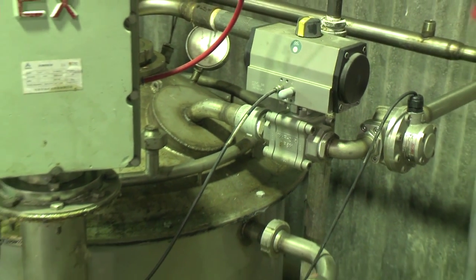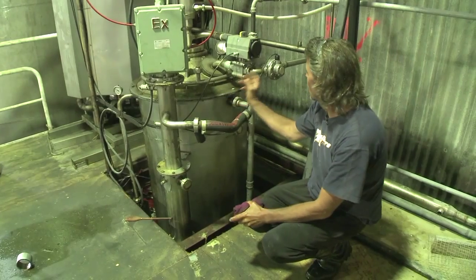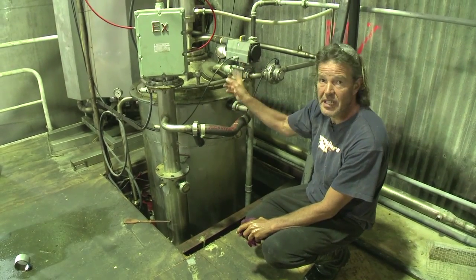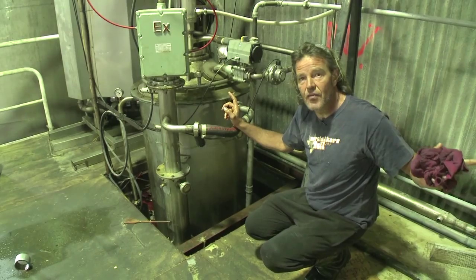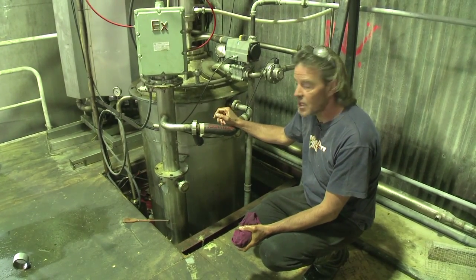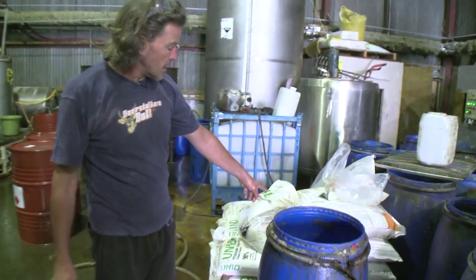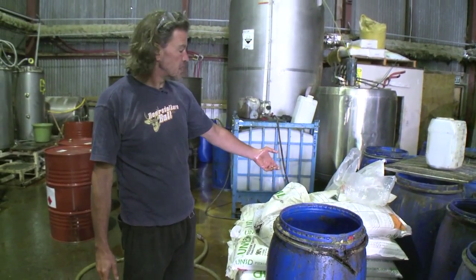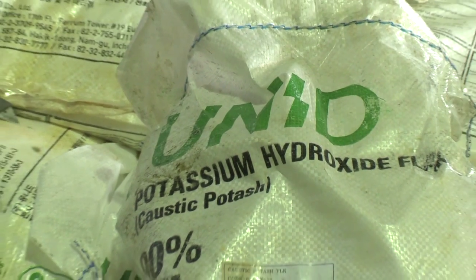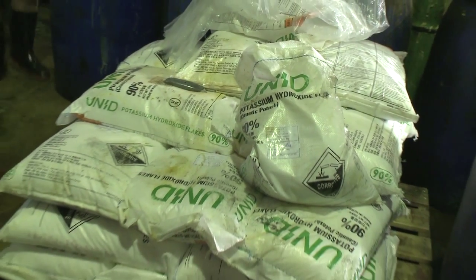We pump the oils around the building into this reactor over here. This is a 1,000-litre reactor — we bring in the oils from the filtration stage, put it through a flow meter and control valve into the reaction system, so we know exactly how much we're putting in. Then the methoxide from the far corner gets metered in at the bottom according to our recipes. We add a certain amount of methanol and then a caustic catalyst — in this case potassium hydroxide — mixed together with the methanol to make the reaction catalyst for addition to the oils.